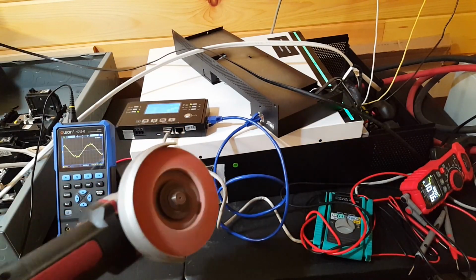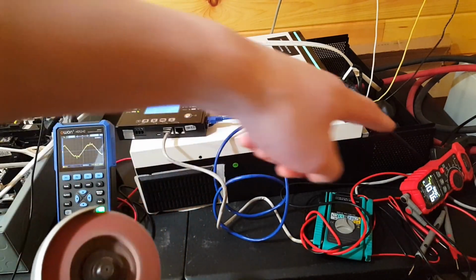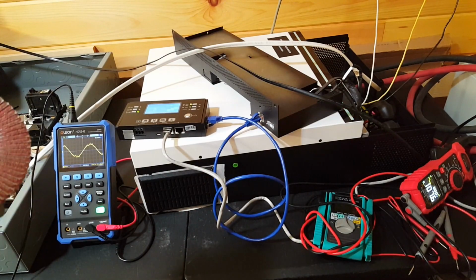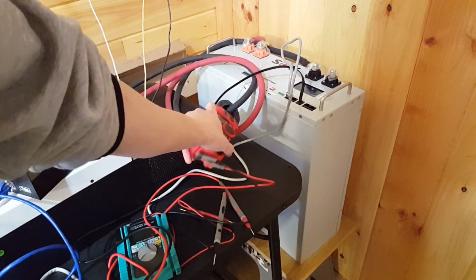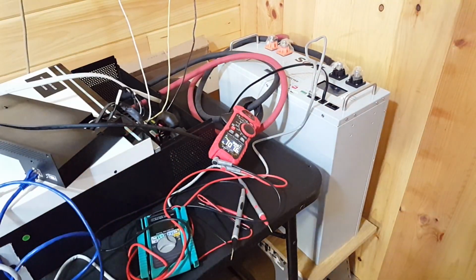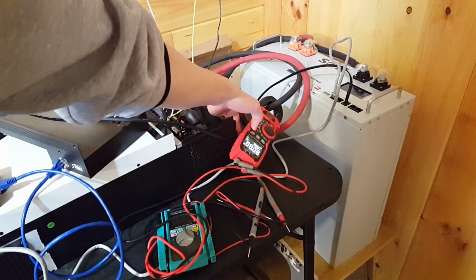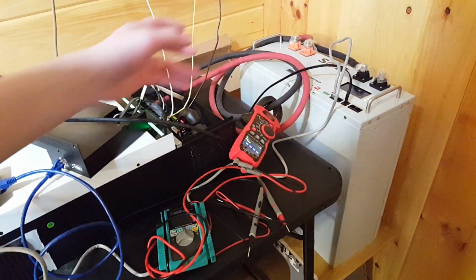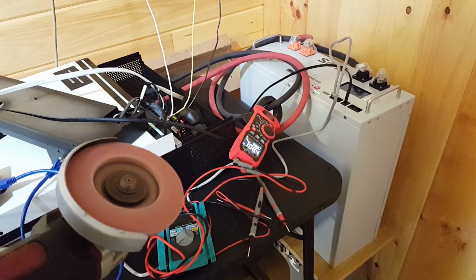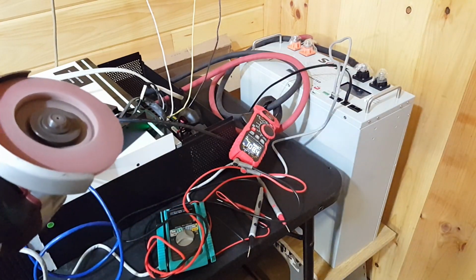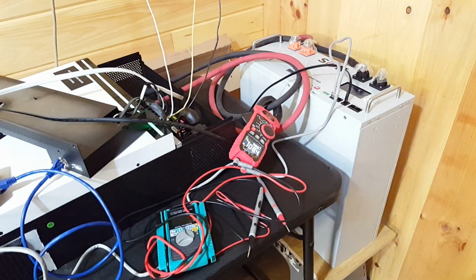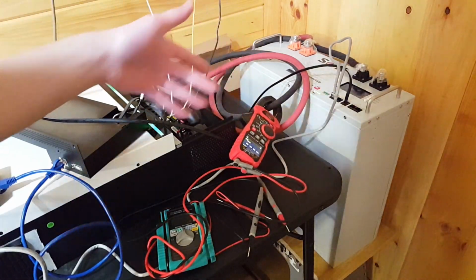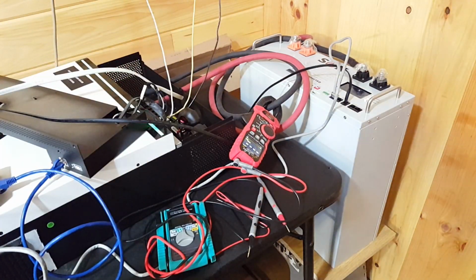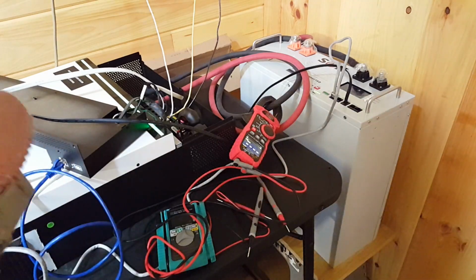Okay. There you go. It did it. 100 amps, 107 amps, a surge. Let's try a couple more times and see if we get like a percent chance failure, just like the air compressor, where sometimes it can start, sometimes it'll fail to start. Test number 2. 108. 108 for the second try. Let's do a couple more times. Let's see if we get a failure on the third, because that's what happened with the air compressor. I'm not confident. Ready?